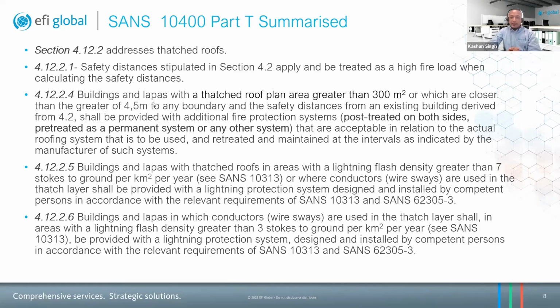Now, however, when looking at a thatch building, the entire roof is considered a combustible fuel load, which poses a risk to neighboring properties as well as to adjacent properties or buildings on the same property. So we see safety distances stipulated in 4.2 shall be applied and treated as a high fire load when calculating safety distances. There is a caveat under table 4.2, or the table within 4.2, where they provide a calculation.